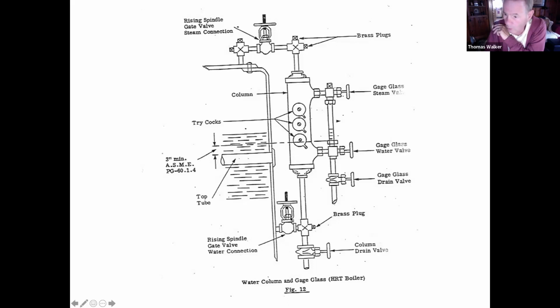So it could be an OS and Y valve. The stem is up, it's open. Or a lever type valve. Attached to the water column could be 3 valves known as try cocks. Try cocks were developed as a secondary means of determining the water level in the boiler. The primary way is by the gauge glass. But if the gauge glass breaks, we got to have another way of doing it. Everybody kind of get that?